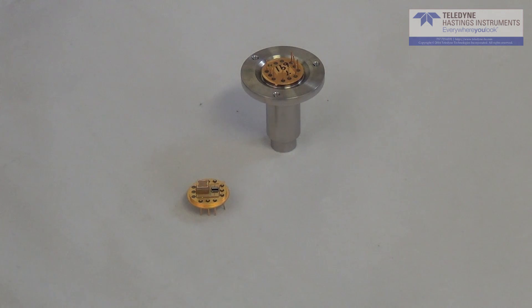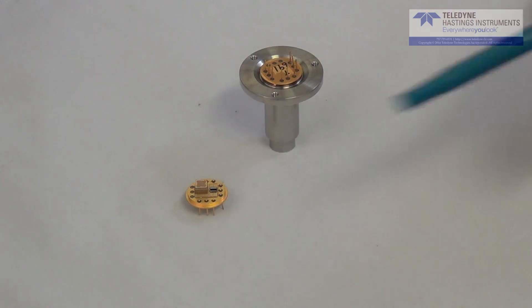So now let's start with the sensors. The 2002 has two micromachined sensors. The larger one is a piezoresistive sensor for measuring pressures up to a thousand torr. And the smaller one is a thermal sensor for measuring pressures down to one millitorr and below.